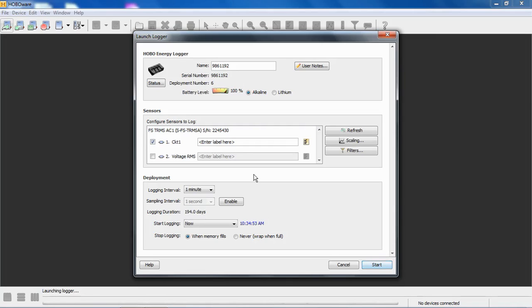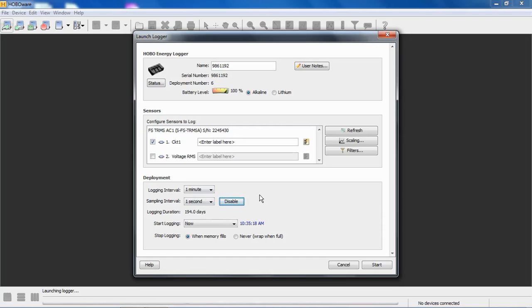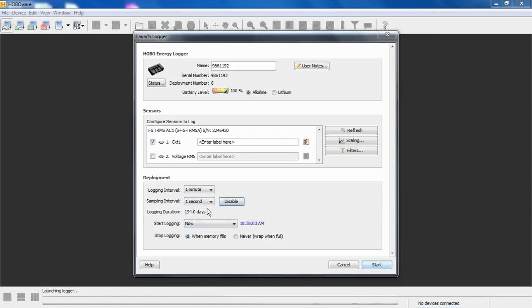One other point too, with the TRMS module, this device does support sampling. So under sampling, we can set a sampling interval for this device. In this instance, with this configuration, with a one minute logging interval and a one second sampling interval, the logger will wake up, basically stay awake the whole time. And it will base the one minute logged data, the interval data, will be based on the average of 60 one second samples. And you can play around with these measurements. The fastest you can sample is once a second. Keep in mind with that one second sampling interval, your battery life will be greatly diminished from the estimated one year battery life if you're just using battery. This particular device comes with an optional AC power source. And when you use that AC power source, the batteries are only used for backup. So if you're going to use this in an application like this where you need to sample every second, strongly recommended you use that AC power source so that you don't lose power.